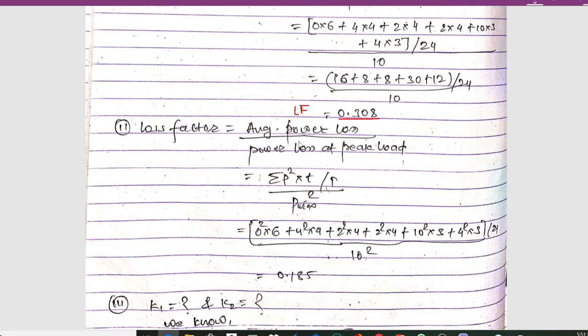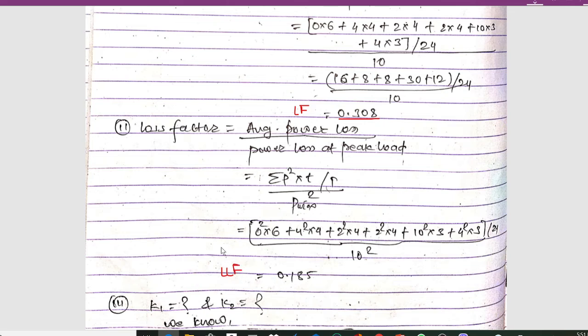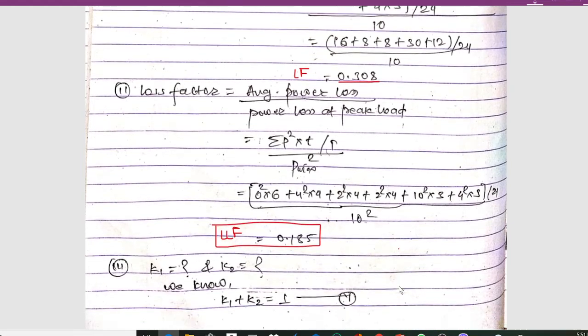To calculate the loss factor, the formula is: average power loss / power loss at peak load. Similar to the load factor calculation, loss factor = summation(P² × t) / T / P_max². So we compute: 0²×6 + 4²×4 + 2²×4 + 2²×4 + 10²×3 + 4²×3, divided by 24, then divided by 10² (P_max squared). Once we calculate, the loss factor comes out to 0.185.